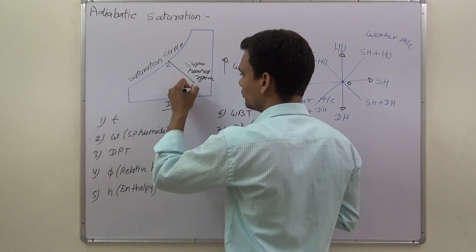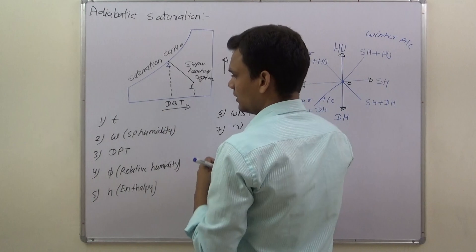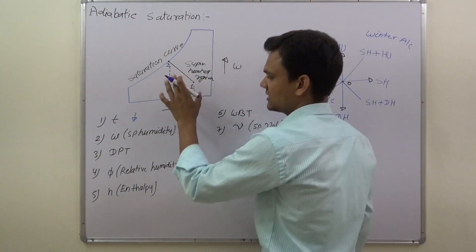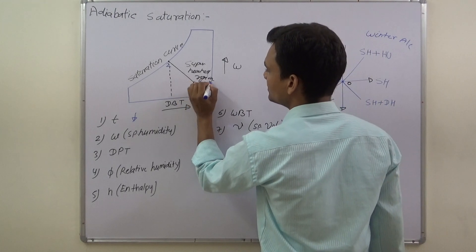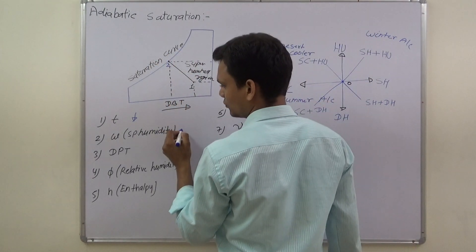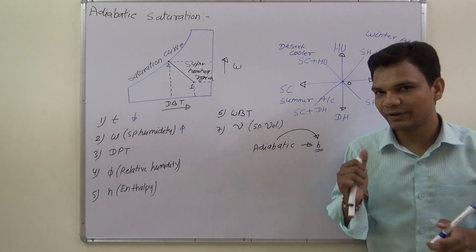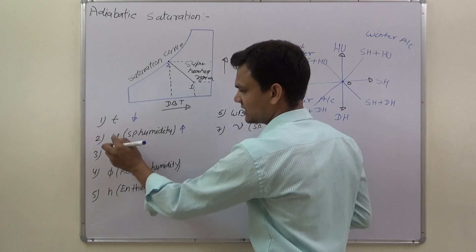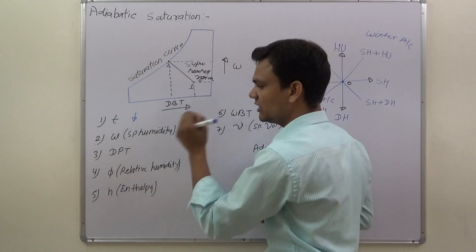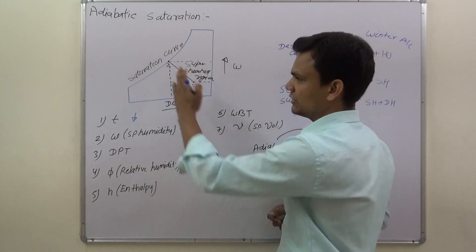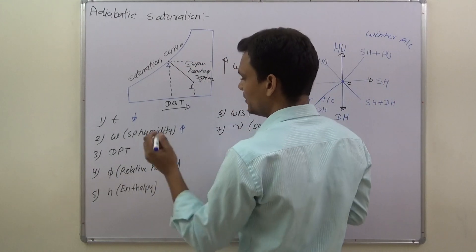So if we go from point 1 to point 2 during adiabatic saturation, the dry bulb temperature will decrease. On the psychrometric chart, specific humidity will increase because humidity lines are horizontal. Dew point temperature lines are also horizontal but are non-uniformly spaced, whereas specific humidity lines are uniformly spaced. The direction of dew point temperature lines is away from the saturation curve, while specific humidity lines move towards the saturation curve. So dew point temperature will also increase.